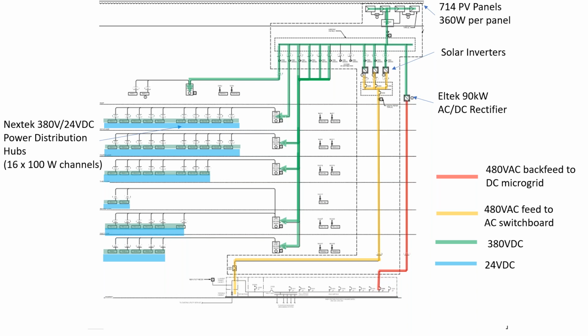The same 380 volt DC bus will also be fed from a second source that supports it during nighttime and cloudy days, because we know the sun is not available 24/7. That second DC source is an AC-DC rectifier fed from the local utility. That is the Eltek 90 kW AC-DC rectifier that will take power directly from the AC and will be able to power the 380 volt DC.